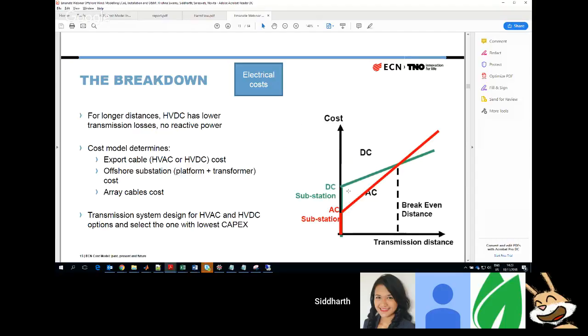So as you can see from the graph, if the transmission distance is lesser, you would generally choose AC, and if it's higher, you would choose a DC configuration. There can be different opinions on what this transmission distance should be. If you do a simple Google search, you can see articles saying a break-even distance of around 70 or 80 kilometers is possible now, but that also depends on the voltage of your cables and a bunch of other things.